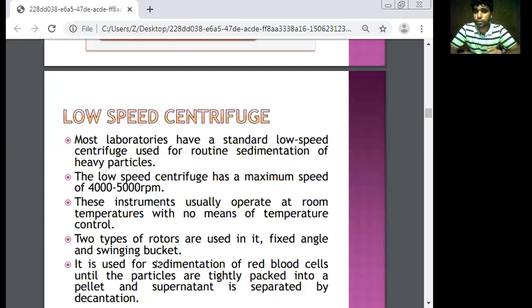The low speed centrifuge has a maximum speed of 4000 to 5000 RPM. These instruments usually operate at room temperature with no means of temperature control. Two types of rotors are used: fixed angle and swinging bucket.